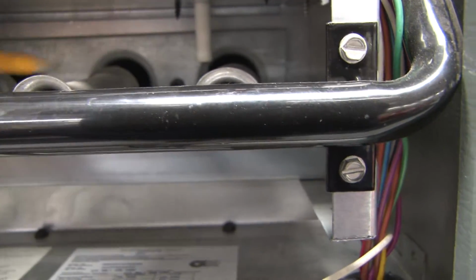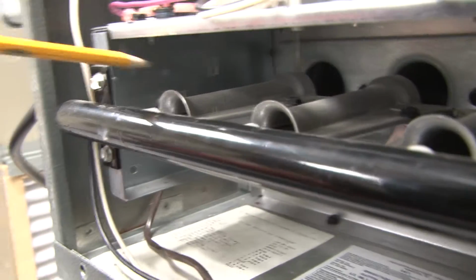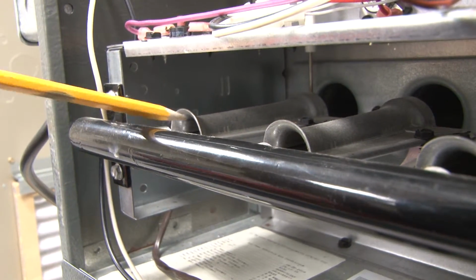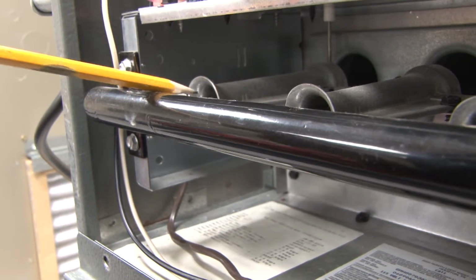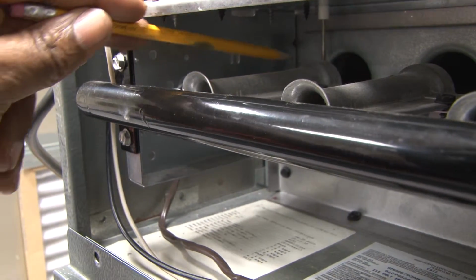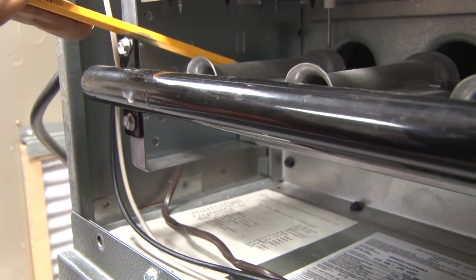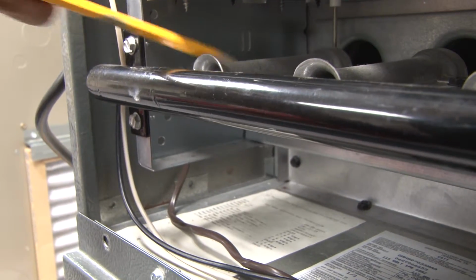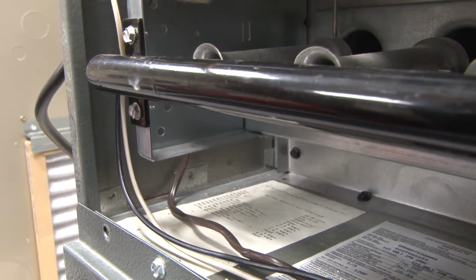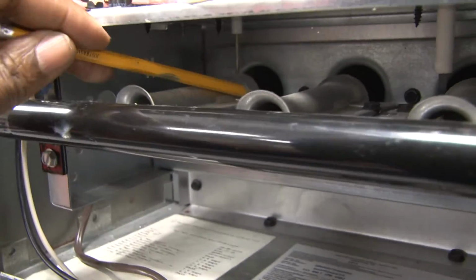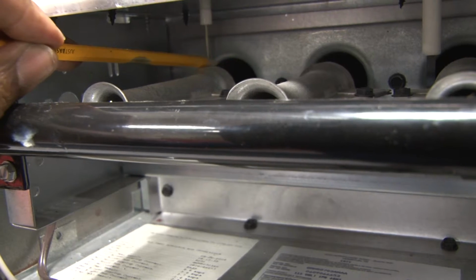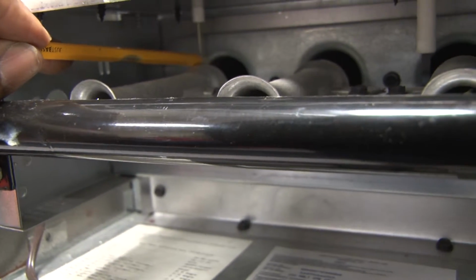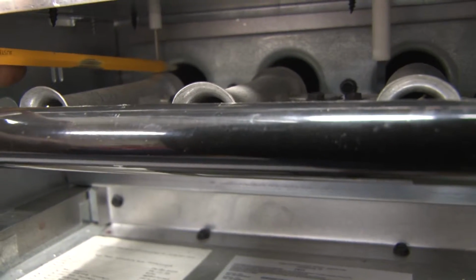As the fuel's mixing, we call that primary air. So it's pulling air to mix with the fuel to cause it to burn on the outlet of the burner. Not the inlet. It's mixing inside of the burner with air and fuel, which we call primary air. As it leaves the burner, it will be ignited, but it also needs additional amounts of air, what we call secondary air.